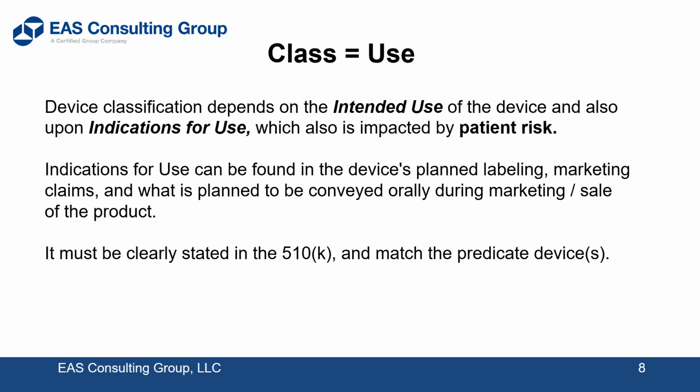You could contract it. In some cases, contraction even requires a new 510K. But indications for use from the FDA standpoint is a legal statement. One of your 21 tabs in your submission is the indications for use. They review that very carefully. And once they clear that, that's it. And your marketing cannot exceed that.